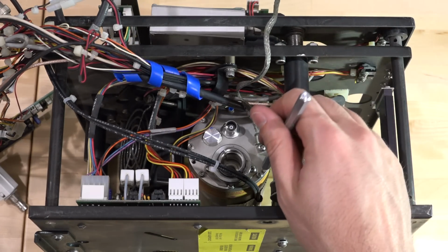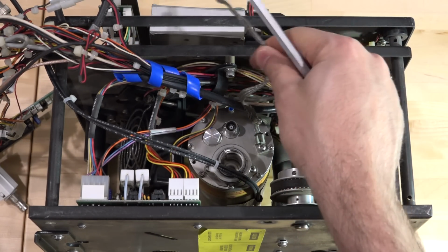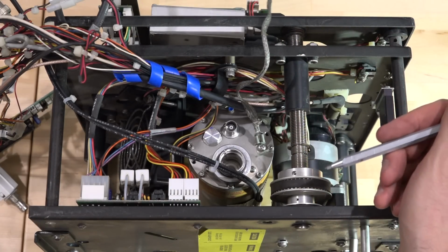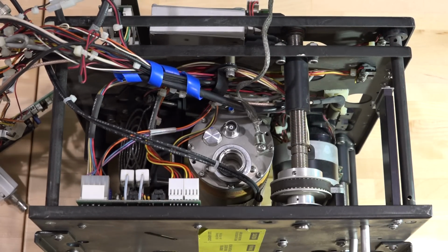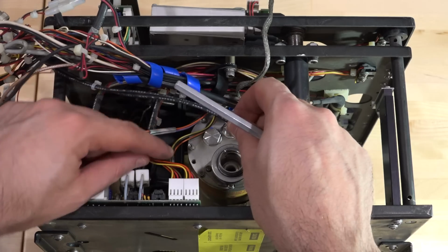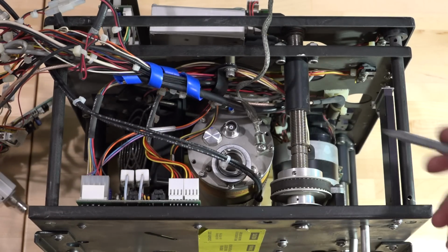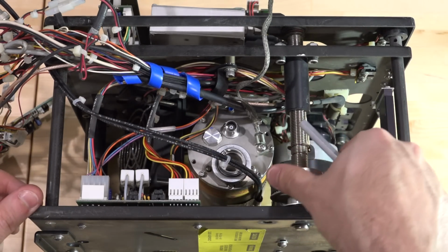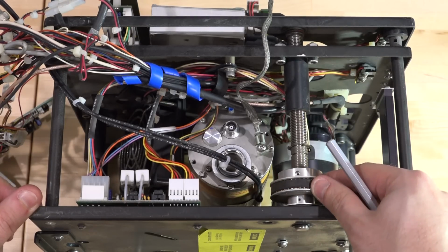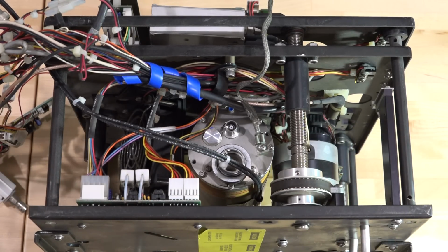And here's the grounding terminal of an X-ray tube. The X-ray tubes are really important to be grounded, and we see this all over the place every time we look at an X-ray unit. There's some controller board over here which connects to a whole bunch of stuff. Nothing really crazy or unusual. Here's the other side of that servomotor you were looking at, and here's one of the belts that it is connected to. Let's turn it one more time.